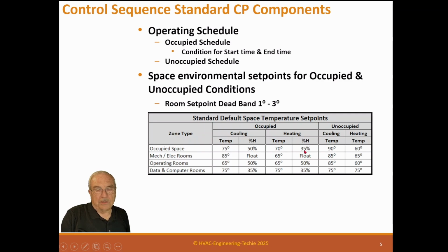And the reason this is lower is because it costs a lot of money to put humidity in a building. In air conditioning, when we take the water out of a coil, we automatically have high humidity. So right off the coil, we're around 50, 49, 48%. So 50% is easy for air conditioning. Depends, though. If you're in the middle of the desert and you've got a lot of sensible heat, you may be down at 30%, but that's the relative idea.